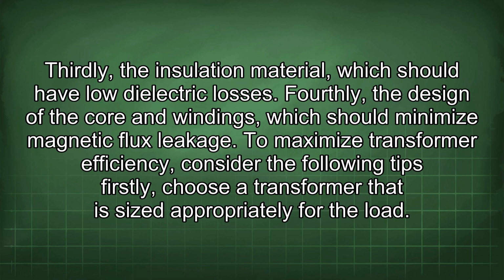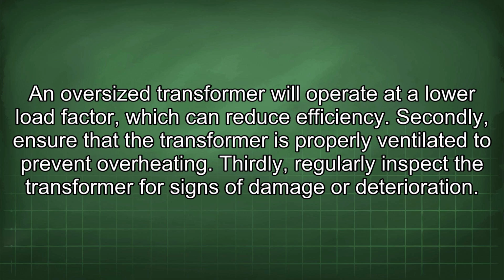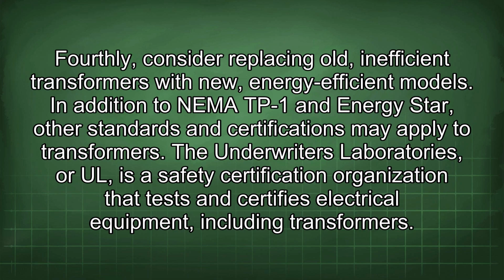To maximize transformer efficiency, consider the following tips. Firstly, choose a transformer that is sized appropriately for the load. An oversized transformer will operate at a lower load factor, which can reduce efficiency. Secondly, ensure that the transformer is properly ventilated to prevent overheating. Thirdly, regularly inspect the transformer for signs of damage or deterioration. Fourthly, consider replacing old, inefficient transformers with new, energy-efficient models.